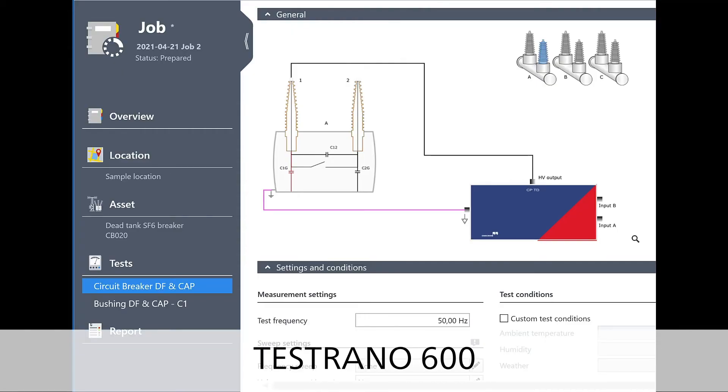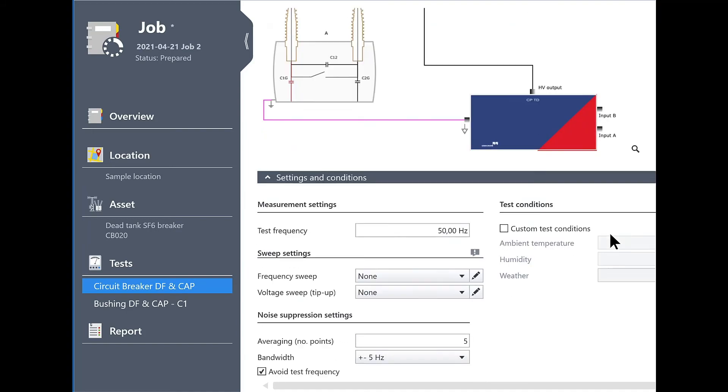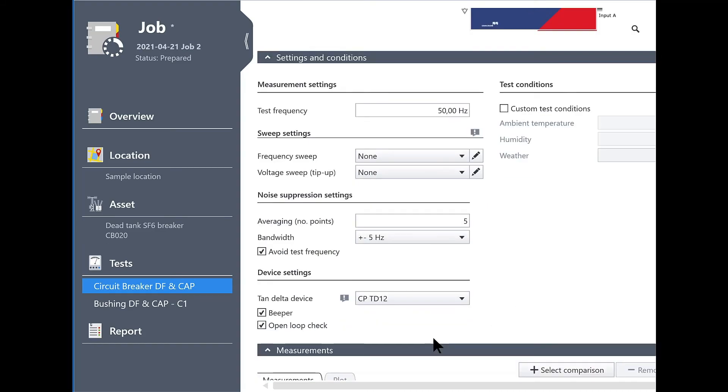For the Testrano 600 we implemented the capability of testing very low capacitances together with CPTD12 or TD15 both in the test set and in PTM. In order to test capacitances in the lower picofarad range the open loop check has to be deactivated. This option has been added here.